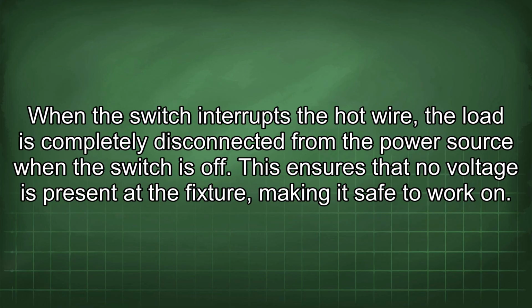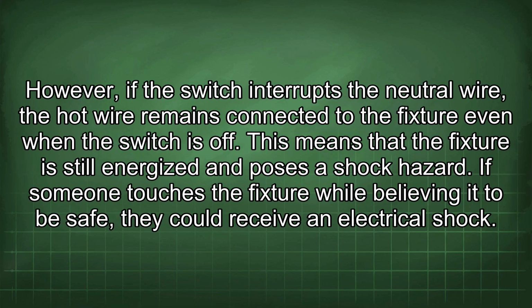When the switch interrupts the hot wire, the load is completely disconnected from the power source when the switch is off. This ensures that no voltage is present at the fixture, making it safe to work on. However, if the switch interrupts the neutral wire, the hot wire remains connected to the fixture even when the switch is off. This means that the fixture is still energized and poses a shock hazard. If someone touches the fixture while believing it to be safe, they could receive an electrical shock.